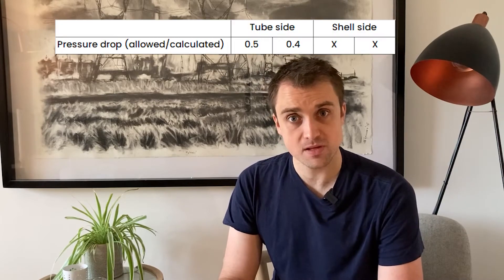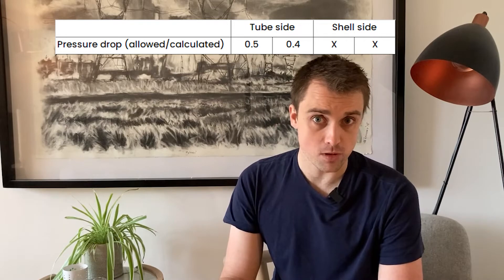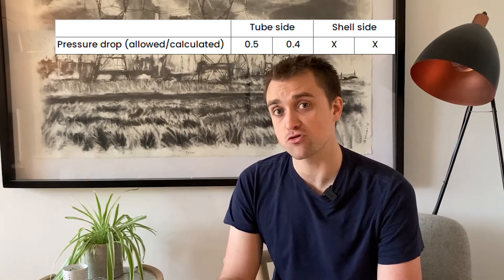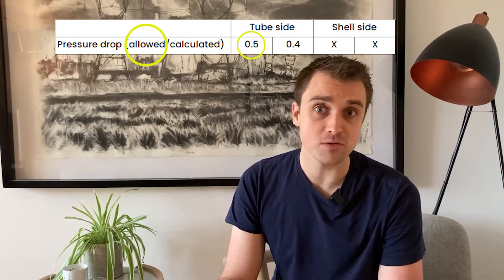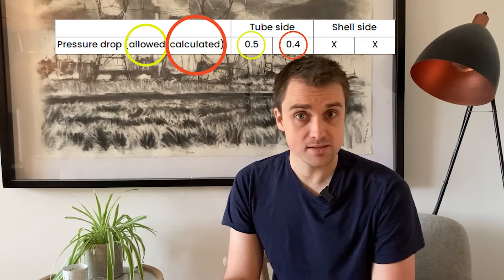Equipment datasheets — most often heat exchanger ones — will usually give two pressure drops: an allowable pressure drop and a calculated pressure drop. In this example, our allowable pressure drop is half a bar, but our calculated pressure drop after sizing the three quarter inch tubes is 0.4 bar. Why is it that datasheets report both of these values?